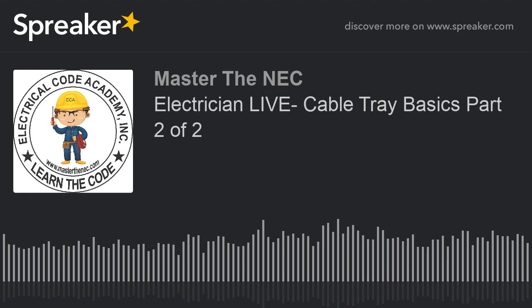It says, the ampacity of single conductor cables shall be permitted by 310.14(A)(2), which we kind of went over. Okay? That's a beautiful thing. All right? It says the adjustment factors in 310.15(C)(1), again, that's for the more than 3 current carrying conductors, shall not apply to the ampacity of cables in cable trays.